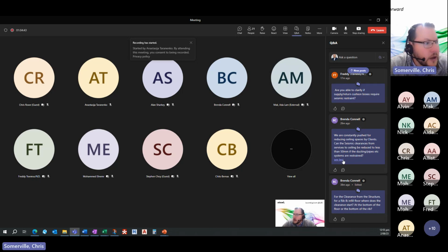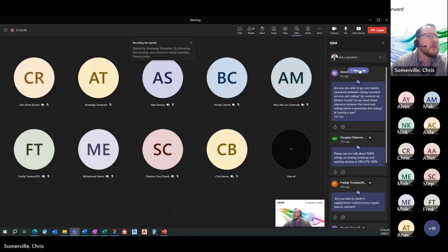Brenda asks: for the clearance from the structure for rib and infill floor, where does the clearance start - at the bottom of the floor or the bottom of the rib? It depends where you're supporting from. If you're supporting from the floor, that's your 400mm, say, for a cable ladder, but if you support from the ribs, that's your support point. Generally, I'd advise not to fix into the infill, depending on the weight of the surface; if it's really light it's probably not an issue, but generally your infill floor is quite thin, so your anchors are very limited in what they can do. There's also debate about whether you can use the ply board itself for capacity, and there are a few checks that have to be done. We'd normally advise fixing into the side of the ribs, or looking at the base of them.